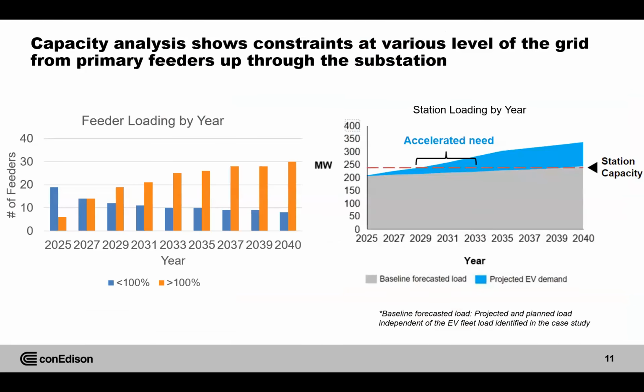Once we applied all the loads and ran our analysis, we ramped it through the years with electrification. The left-hand graph shows feeder loading by year—these are the 13 kV distribution feeders Cora mentioned, about 30 in the network. The blue bars are feeders not currently overloaded, and the orange bars are feeders that would overload as electrification ramps up. By 2040, a majority of our feeders are overloaded.